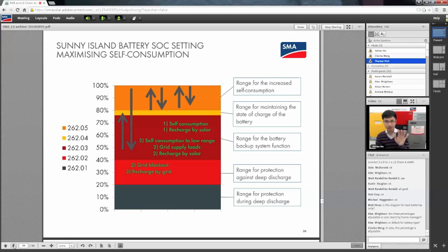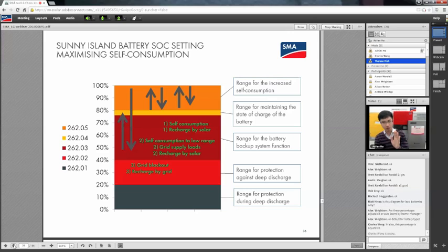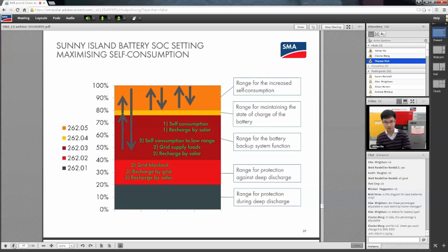The grid then remains supplying the loads, but not further charging the batteries, only up till the next morning when the sun kicks in - then the solar will bring it further up, back into the self-consumption orange range. All these percentages are adjustable; I've just used these as an example for our lab testing lithium-ion batteries.